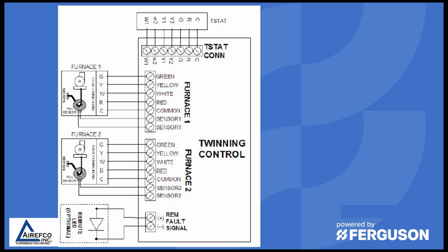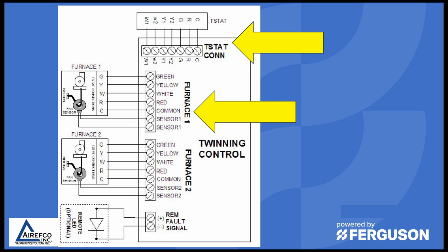There are also twinning kits that are solid state, where you just make your thermostat connections and connections to furnace 1 and furnace 2, and you're done. You don't have to install field installed relays or transformers. It's all done on the twinning control panel that's already pre-wired and has the electronics to accomplish what you need to do with a twinning system.